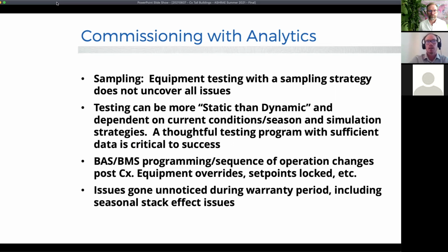But with a building automation system that's looking at these, or using analytics, we can look at set point versus actual. We can look at other basic information and confirm whether or not there's an issue, whether we have a damper issue. If we're looking at return air, mixed air, supply air, outside air, exhaust air, and something's not quite right, that's an insight that could be generated, and we can do something about it.